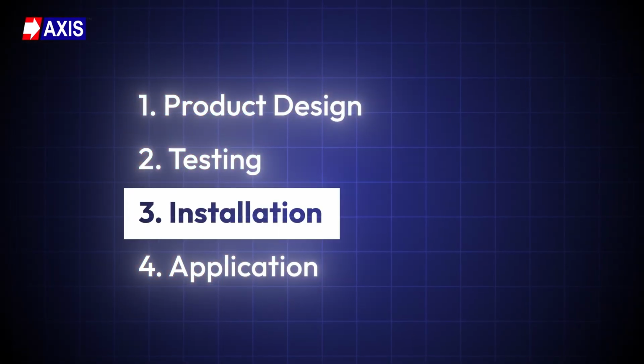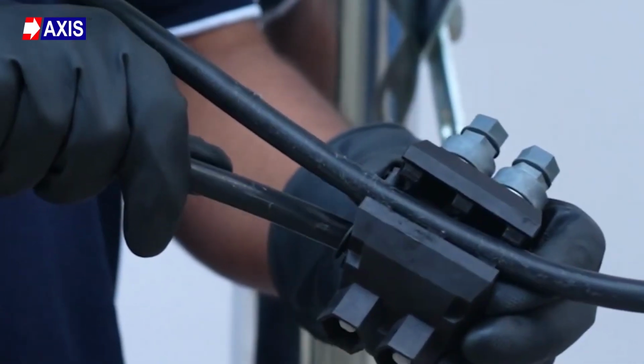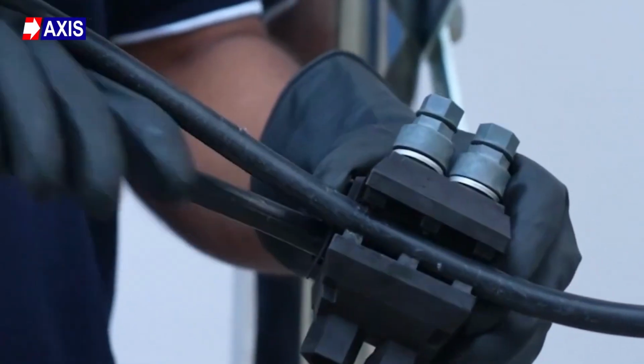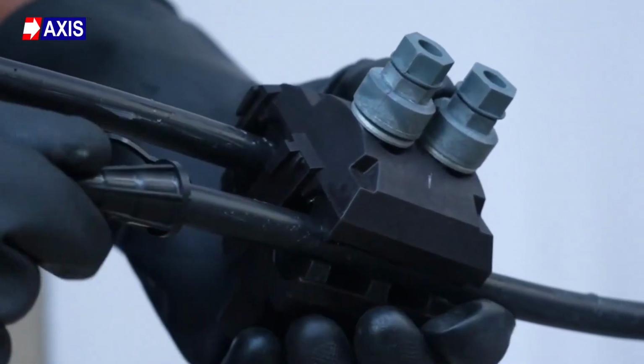Now, the installation of the IPC. Even a well-designed product can become unsafe if it is installed incorrectly. You must use insulated tools which are specifically designed for live line working. The installation should be done under off-load conditions where the main line is live but the branch cable is still de-energized at the moment of connection. Initially, the branch cable should be inserted inside the connector and the exposed end of the branch cable must be sealed using the insulated cap.